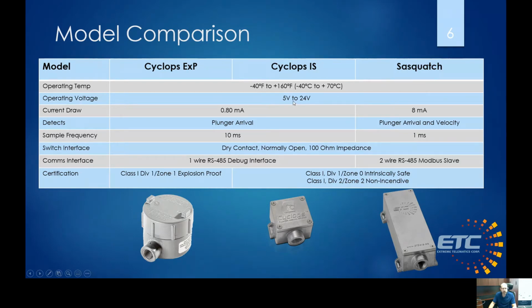Now, they both work the same way. You can use a wide range of operating voltages up to 24 volts. It uses less than a milliamp of current consumption, and it will just detect the plunger arrival. So we sample at about 10 milliseconds frequency, and then the dry contact, which is normally open, gets closed on arrival. There is this one-wire RS-485 debug interface, and that's how we interact with Vision. So this isn't used from an operational perspective. It just allows us to configure the sensor or to monitor the sensor or upgrade its firmware.